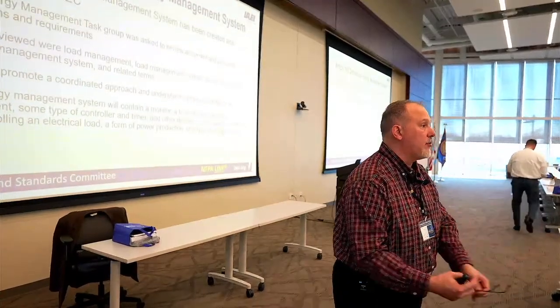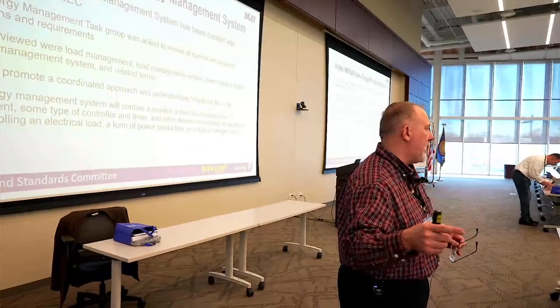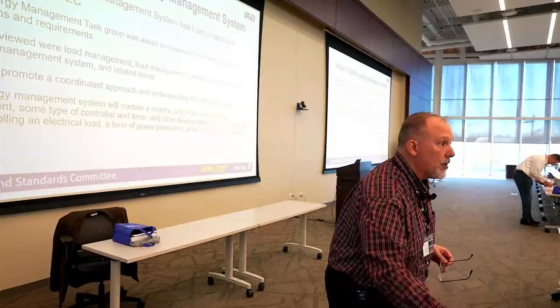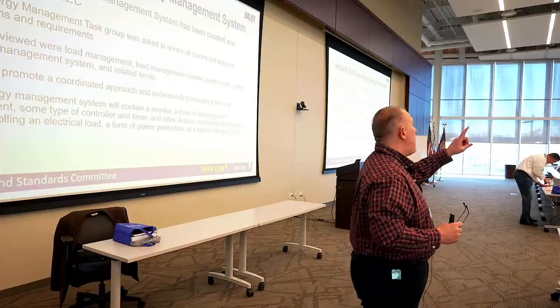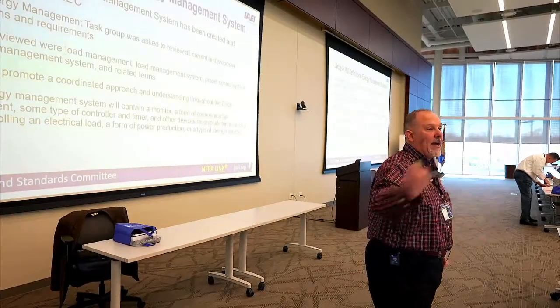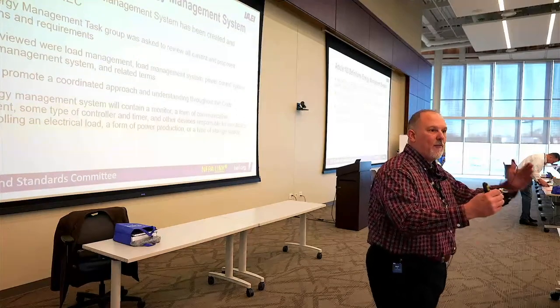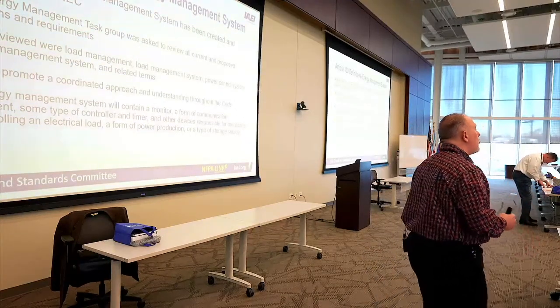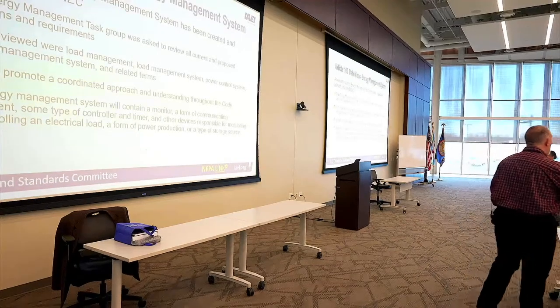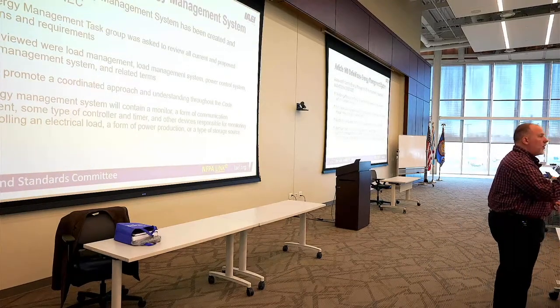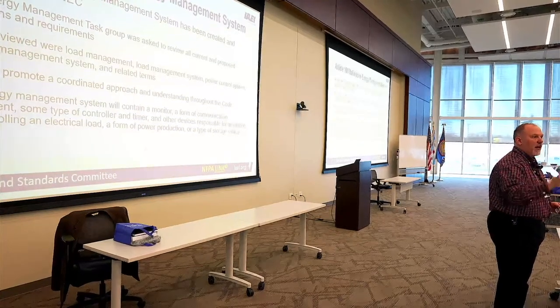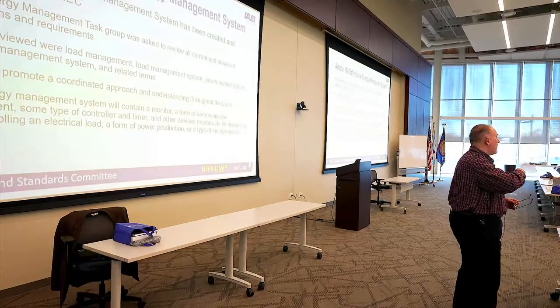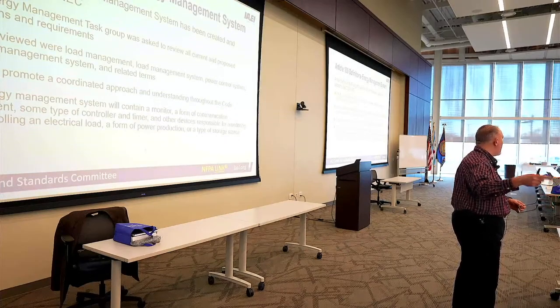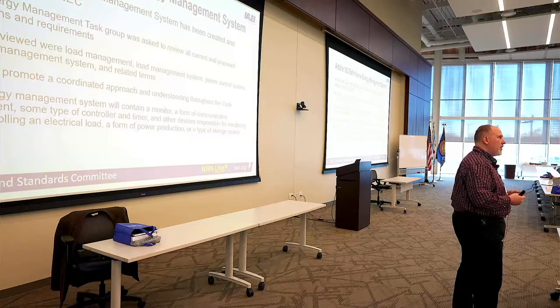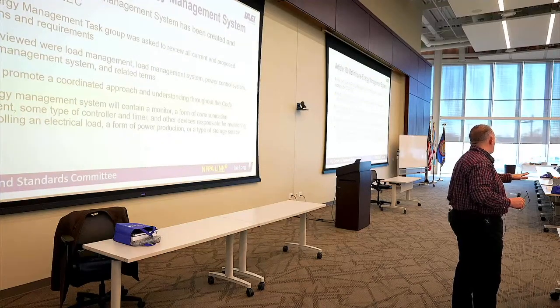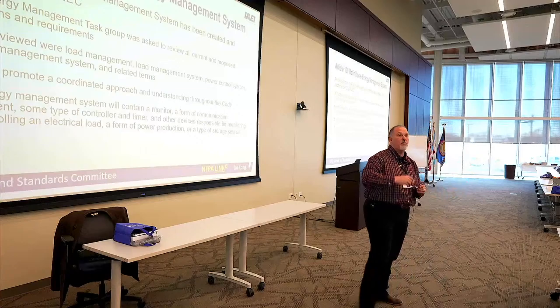You've got electric vehicles that want to power the house, solar photovoltaic systems that want to provide power to the house, energy storage systems that want to provide power to the house. We have in Article 702 a requirement that your backup generator has to be sized for the load, and we have load shedding, right? So load shedding could be considered an energy management role, because what are we doing? If I go to the generator, I'm going to shed some of my loads to make sure that my generator is able to supply the loads when I have an automatic transfer switch as required in 702. So we could call that an energy management system — we could call what we're doing in 220 energy management systems when I'm doing my load calculation.